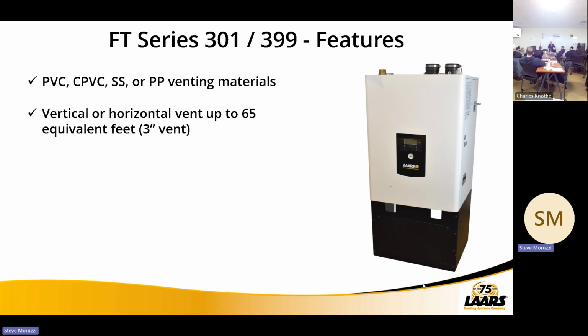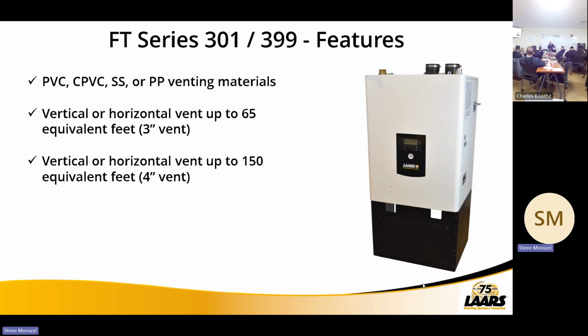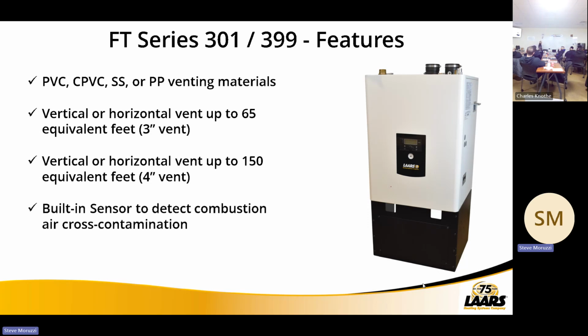All right, so vertical or horizontal venting up to 65 feet and 3-inch. If you want to go greater than 65 feet, increase that vent to 4-inch. We can go up to 150 feet, and that's each. That's not combined, okay? And then follow the instructions on how many feet per fitting, etc. So now we offer you up to 150 feet on the 301, 399. We have that built-in sensor now to detect cross-contamination. This is the only product we have it on currently, right? And that is really a negative cabinet, which I'll talk about in a few minutes.